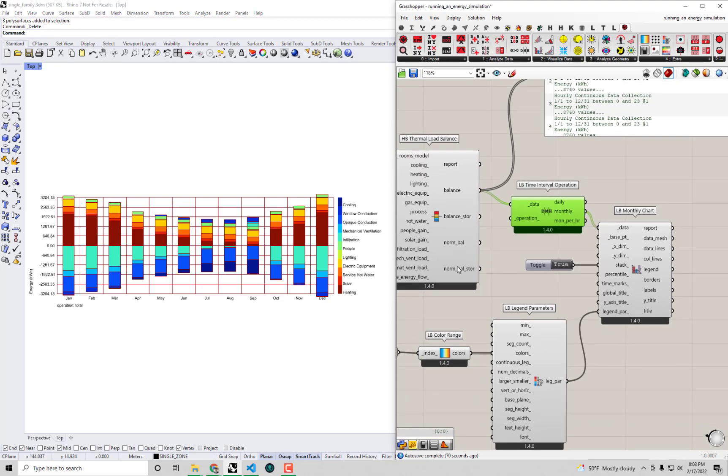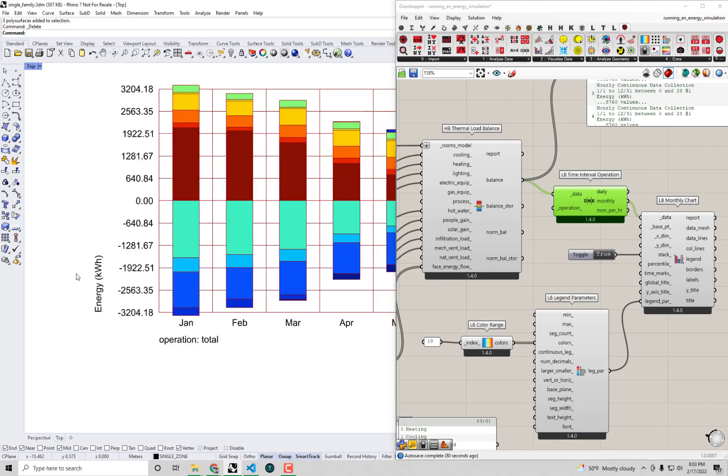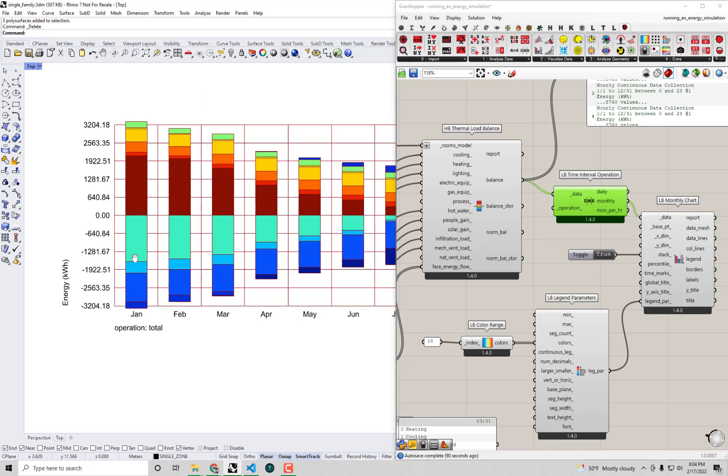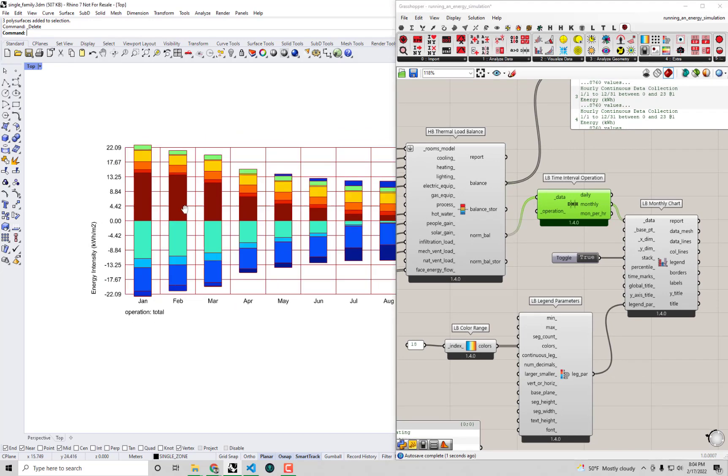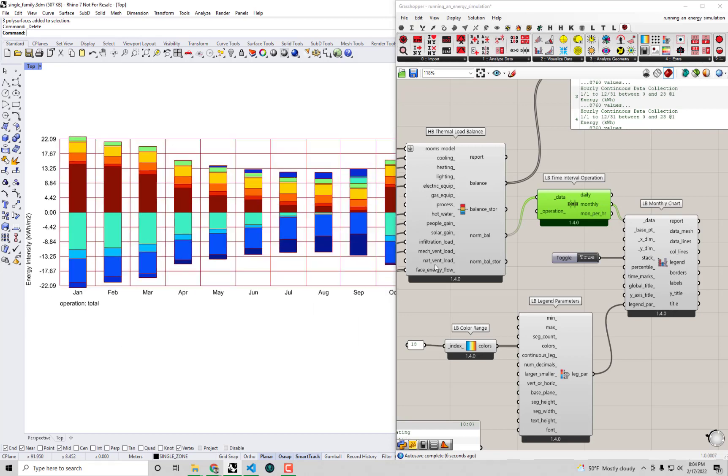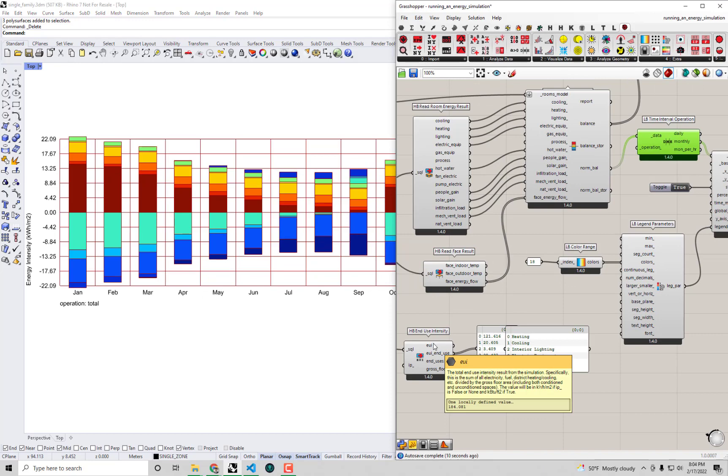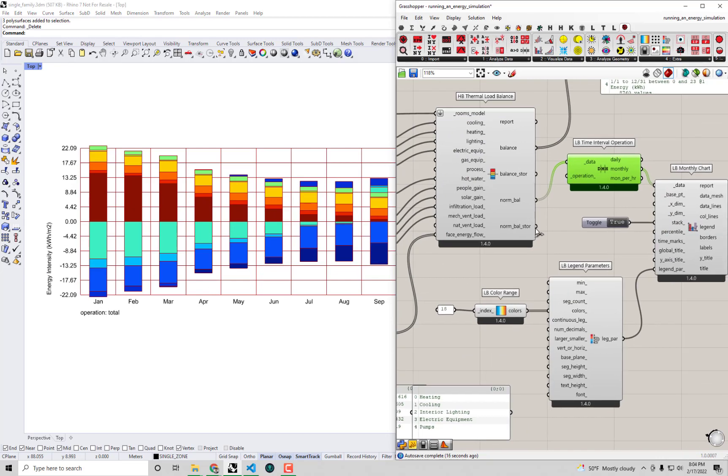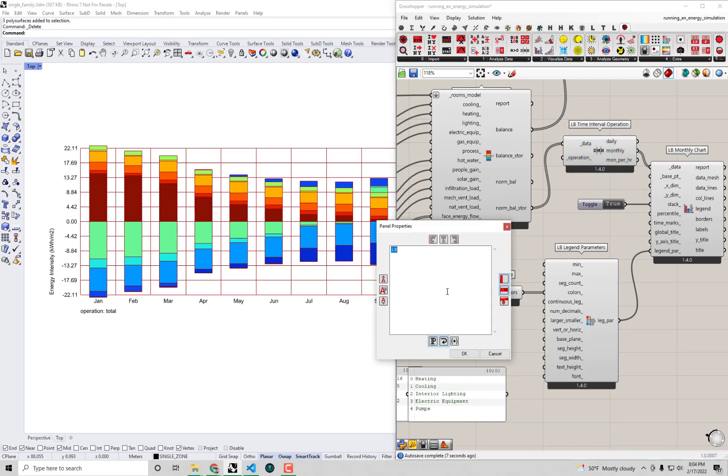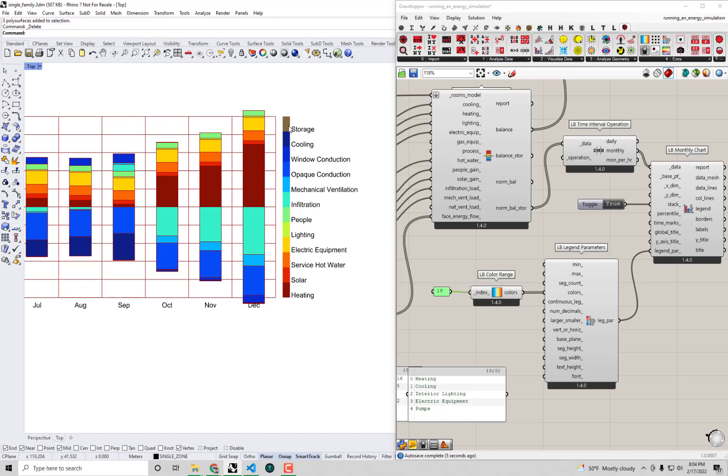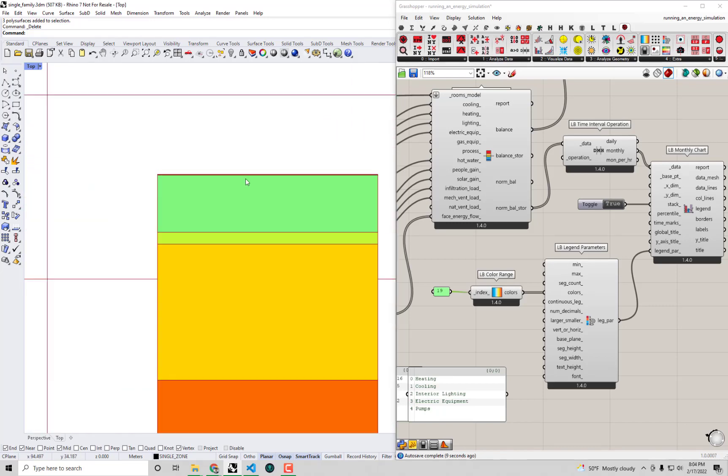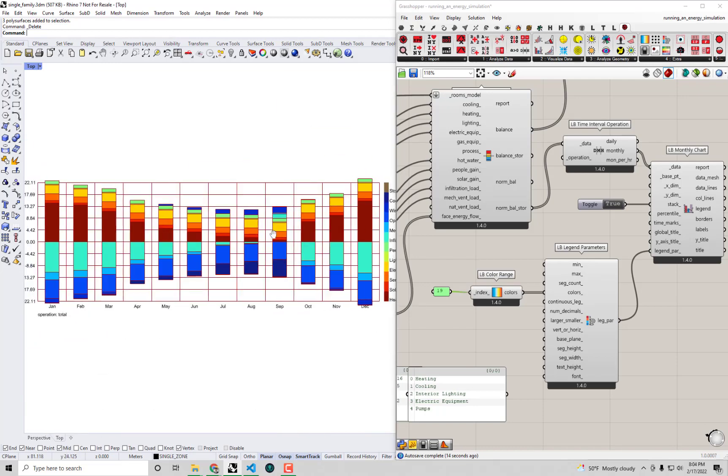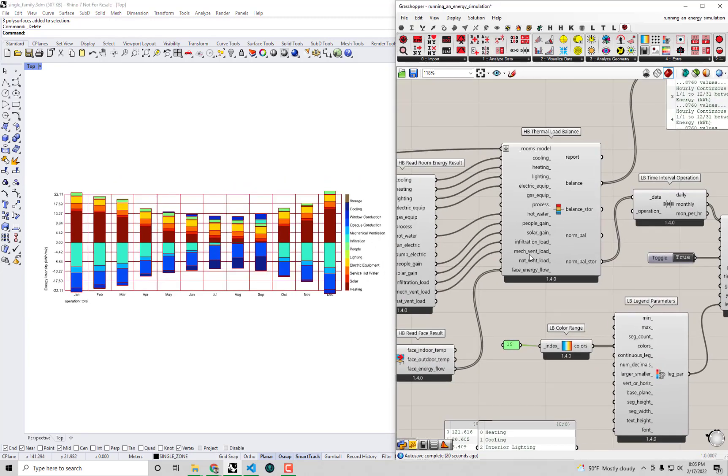Maybe I'll just show you guys one other thing, which is this normalized balance with storage. So right now we're just looking at the total number of kilowatt hours for each month, but it's often a lot nicer to look at the energy intensity in kilowatt hours per square meter instead of just the sum total kilowatt hours. So that's what this floor normalized balance here does. And you can see that the numbers are a little bit more close to what we'd expect. And if you summed it up over all these months here, you'd get something closer to our total EUI here, which is 184 kilowatt hours per square meter. And you can also add an extra storage term, which I can show you this quickly. All that's going to do is that I'm going to use the normalized balance with storage and I'm going to change the color range to be 19 instead of 18. And you'll see that whatever is left over, whatever is not perfectly balanced will get labeled in this brown color. And usually this term should be very small. We can see there's a very little bit that we're getting in some of these months, but this is usually a good sanity check to make sure that the simulation is truly balanced and that you've connected up all the inputs that you wanted here.